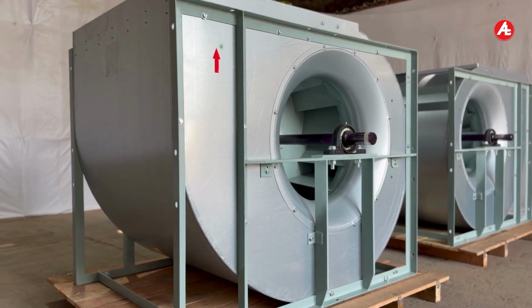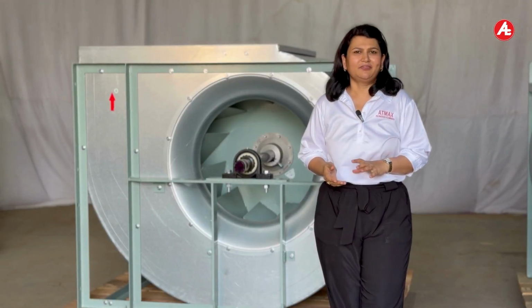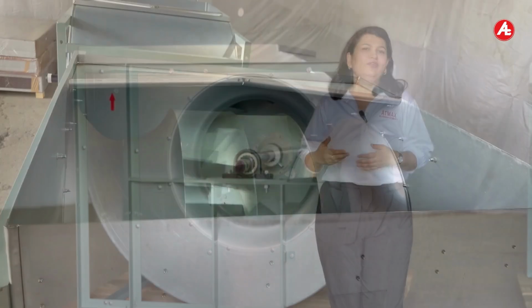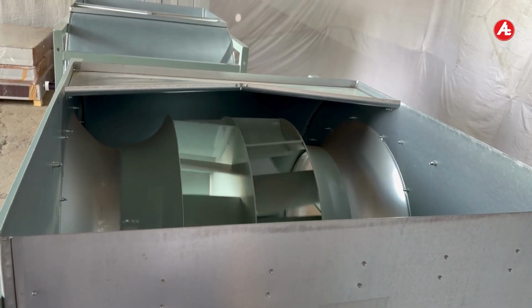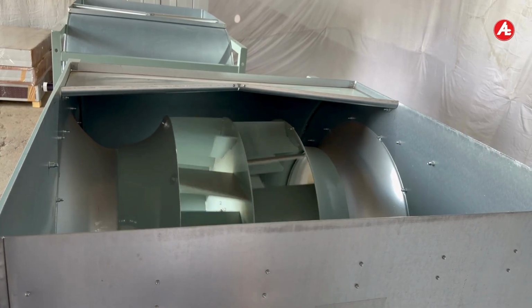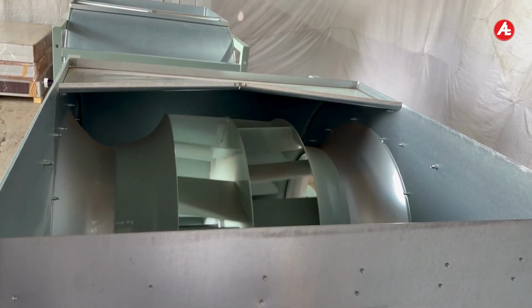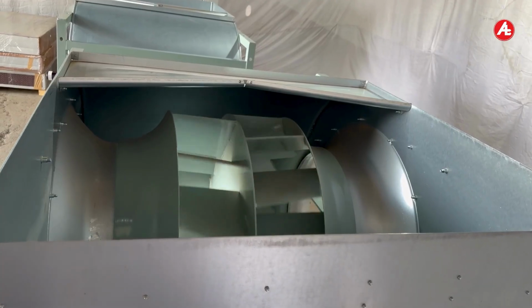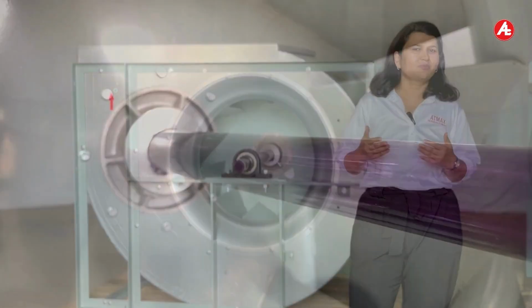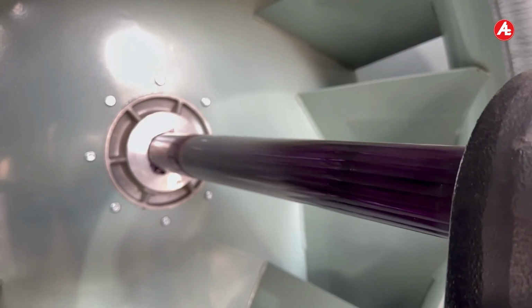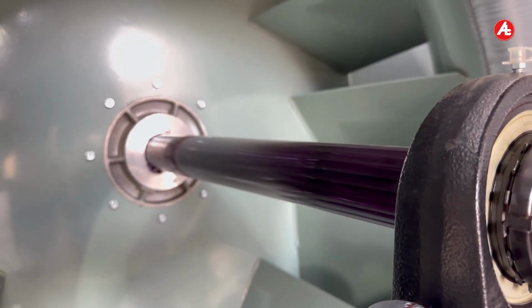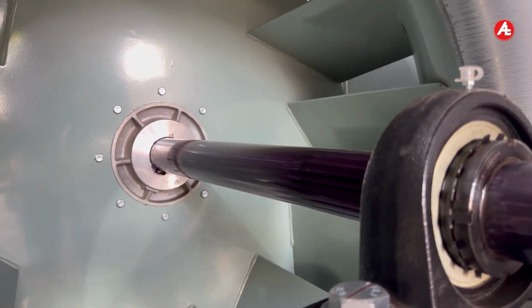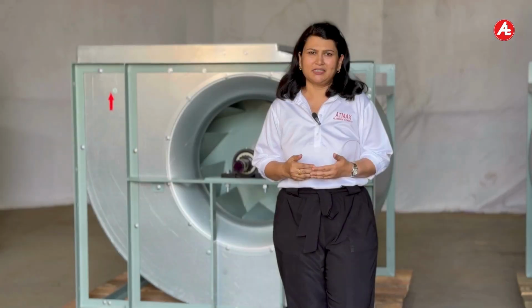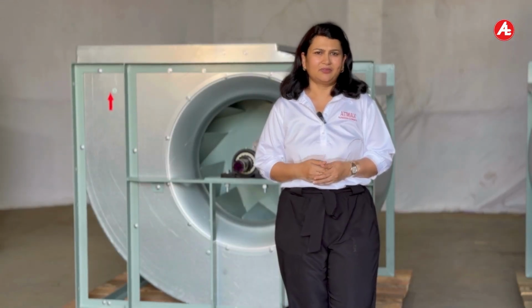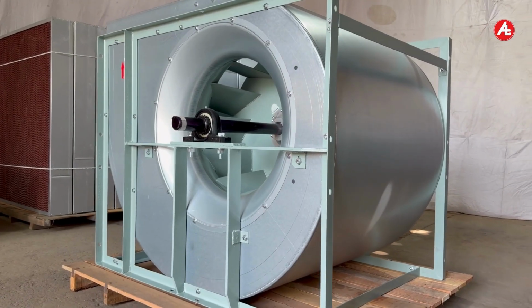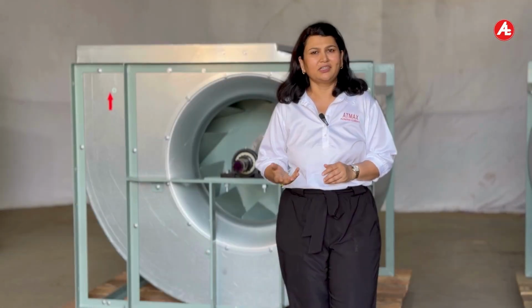Why DWDI? Because a double width double inlet fan increases airflow capacity by at least 30 to 40% with just one motor, which automatically brings down both your capital and operational costs. It consumes much lesser space since you're not increasing the number of fans. Noise levels are lower, and this special symmetrical airflow brings more mechanical and geometrical stability, which extends bearing life. You also reduce power consumption because you're using just one motor for the increased airflow.